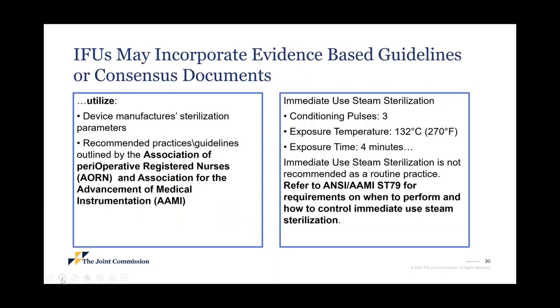Now, you just saw in the example that the instructions for use may incorporate certain evidence-based guidelines or consensus documents. For example, the manufacturer on the left says, follow the device manufacturer's sterilization parameters. And they also say, follow recommended practices and guidelines outlined by AORN and AAMI. But they don't tell you which specific ones. So in that case, you're going to follow the manufacturer's specific instructions for use. And if you need more information about recommended practice or best practice guidelines, you can go to AORN and AAMI.